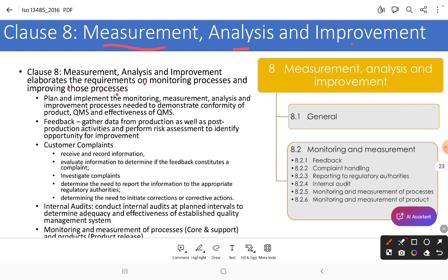So it includes the feedback, the information gathered from production as well as post-production activities, and performing risk assessment to identify opportunity and improvement. Customer complaints, okay, so for a customer complaint, review and record the information, evaluate the information to determine if the feedback constitutes a complaint, investigate the complaint, and determine the need to report the information to appropriate regulatory bodies. So let's say if there is any adverse event, those should be reported to the appropriate regulatory authorities. Determine the need to initiate corrections and corrective actions. So those should be evaluated during the complaint.